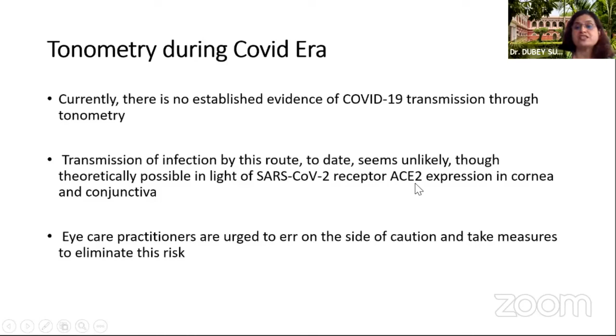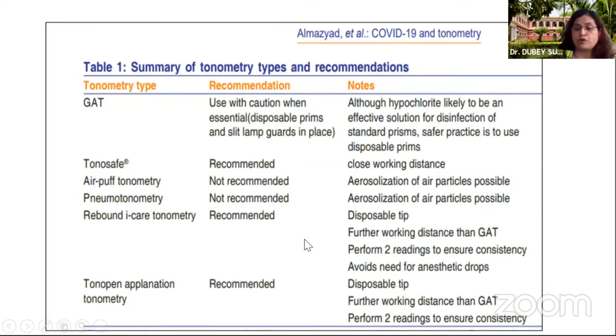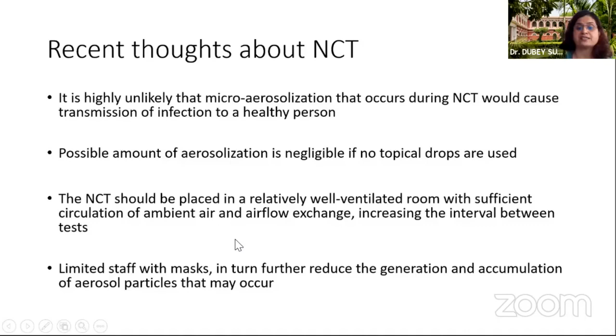This review was done in 2020, and at that time they advised against the use of air puff tonometry and pneumotonometry, and the rest all could be used with proper disinfection. However, recent thoughts about NCT is that it is highly unlikely that microaerosolization that occurs during NCT would cause transmission of infection to a healthy person. Possible amount of aerosolization is negligible, especially when no topical drops are used, because the tear film volume is very small. And if at all you have to use NCT, it should be placed in a relatively well-ventilated room with sufficient circulation of ambient air and air exchange, and increasing the interval between the two tests, and with, of course, limited staff who are wearing masks. So it will further reduce the generation and accumulation of aerosol particles.